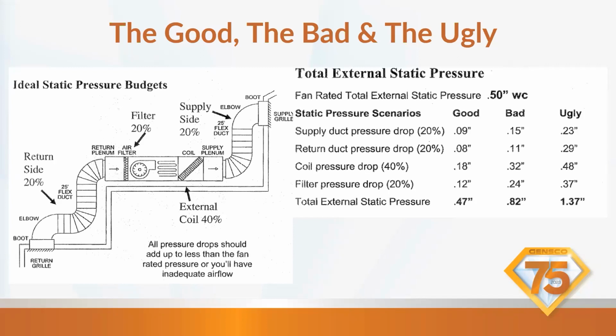That's possible. If you've got a zoning system that has one of the dampers failed, is it a Honeywell zoning system with a... I can't think right now, not the backdraft damper, but the bypass damper. Is it stuck open so the supply air is going right back into the return air, or should that damper be open for the relief damper, and is it working correctly? We can tell that with our static pressures, so keep that in mind.